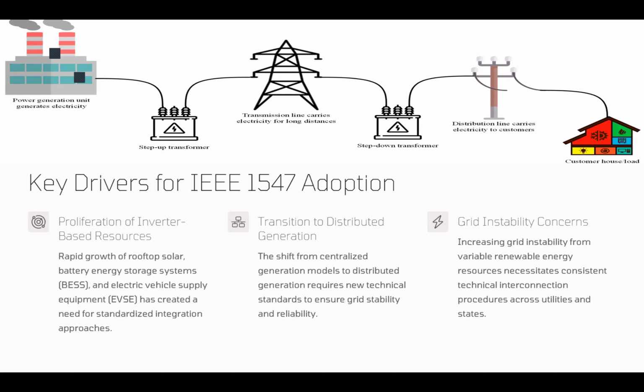Now, we said we are going through a shift to the modern power grid. So there is a transition to a different topology and a different nature for our power system. This is a transition to distributed generation. The power grid is shifting from the centralized generation model, which was large power plants transmitting electricity in one direction, to distributed generation, the DG model, where we have many small resources that generate electricity closer to the loads. One of the major challenges is that those distributed generators introduce bi-directional power flow. This is one of the main differences between the traditional centralized model and the distributed model for the power system. Before, we had a unidirectional flow. Now we have a bi-directional flow.